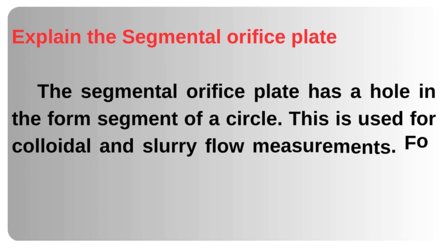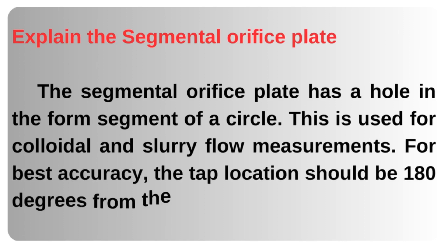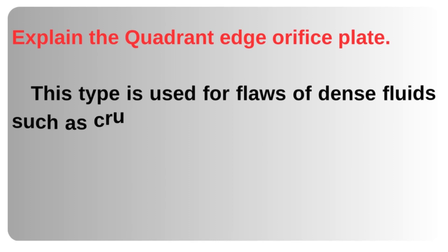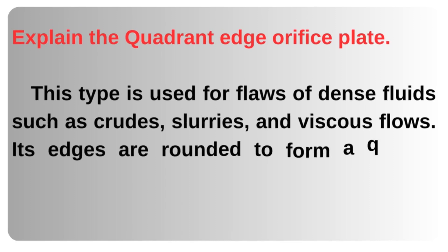The segmental orifice plate has a hole in the form of a segment of a circle. This is used for colloidal and slurry flow measurements. For best accuracy, the tap location should be 180 degrees from the center of tangency.